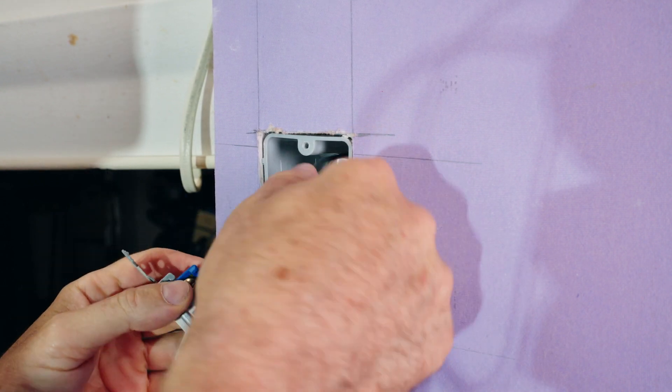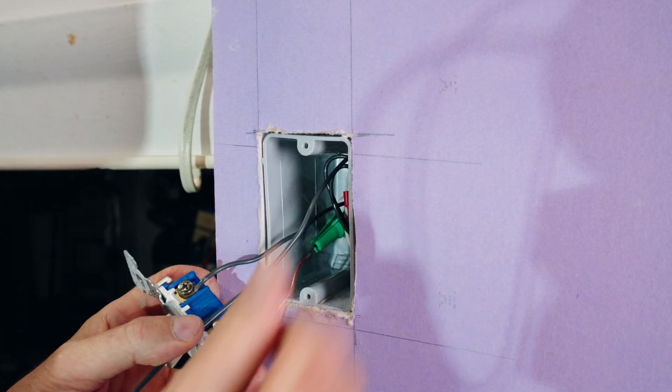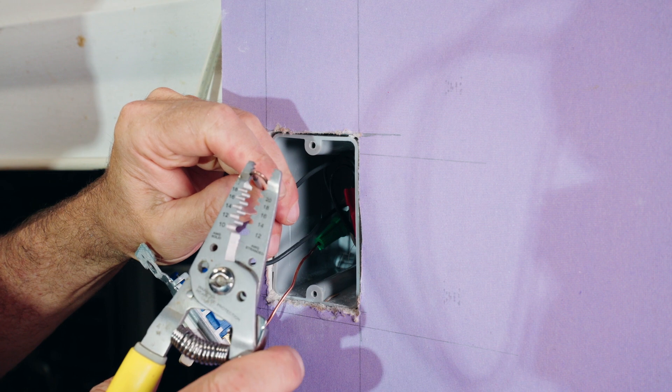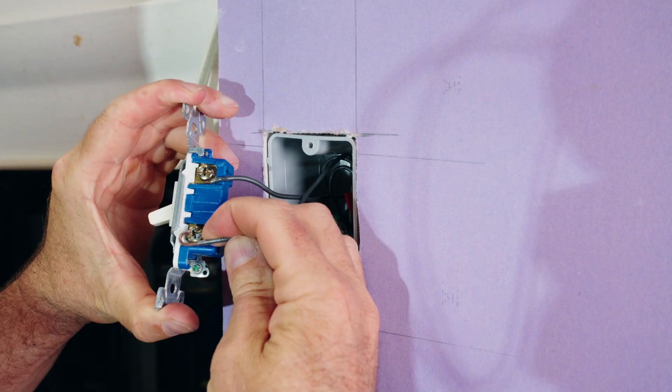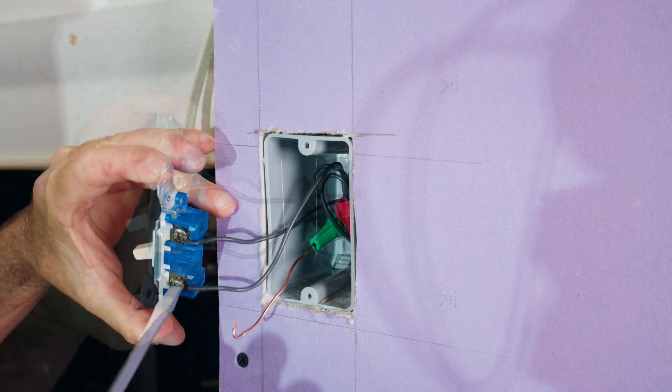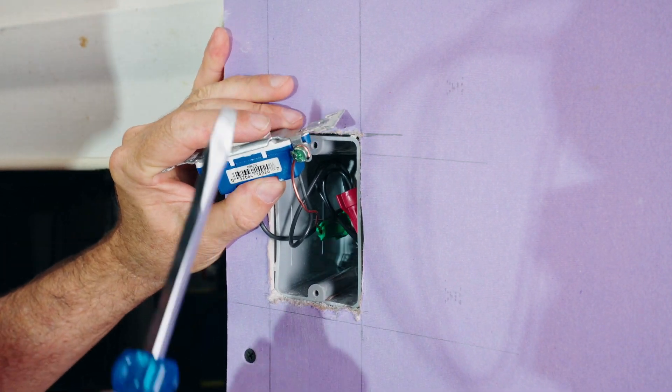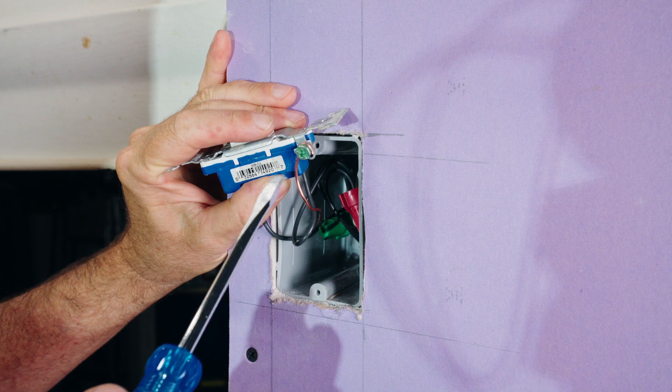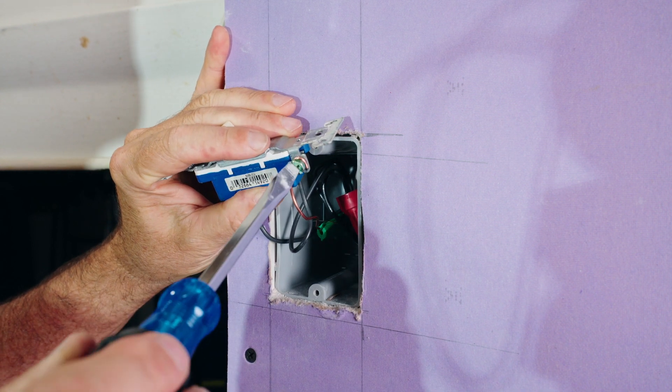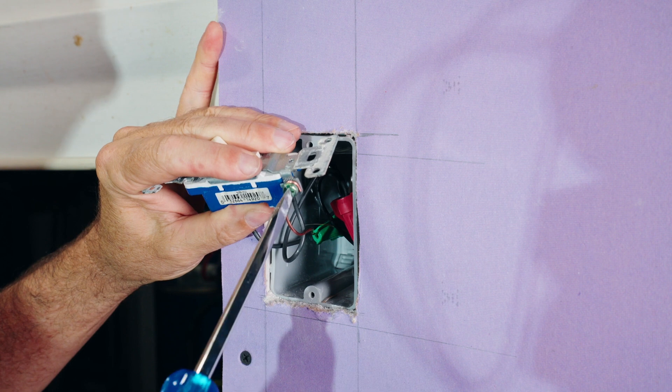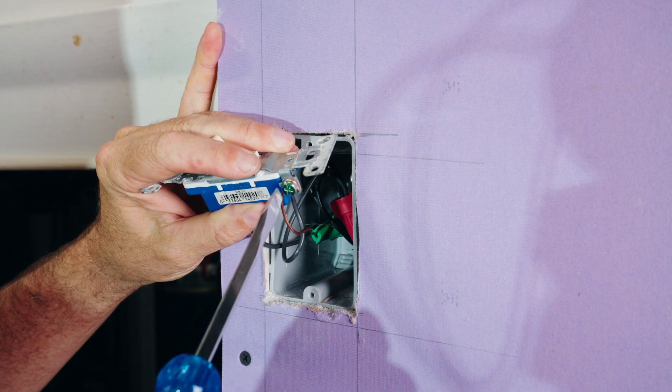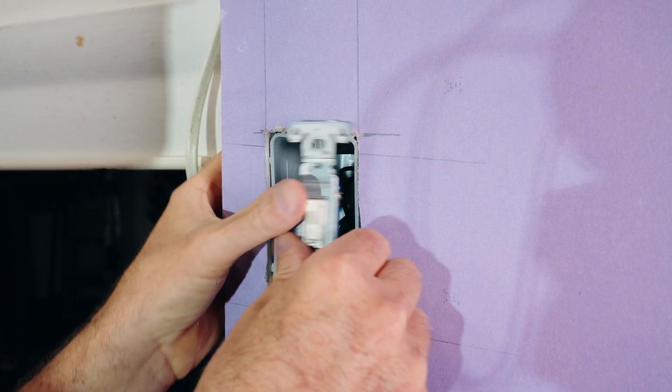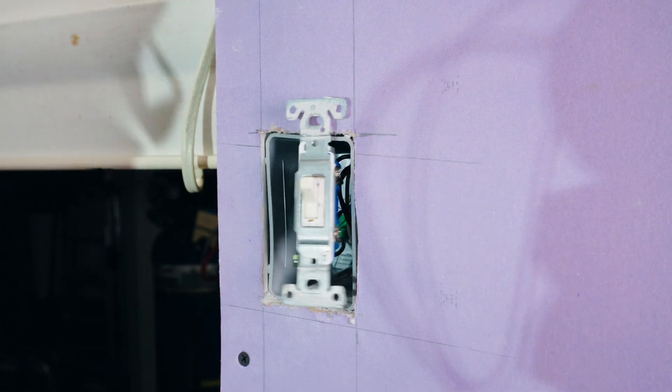We'll go ahead and cut this off so that it's equal with the other one. Bend it into a loop and connect it to our switch. By the way, if I didn't mention it earlier, when you're doing the loops on any connection, make sure the loop is going in the direction that the screw tightens. Because otherwise, when you tighten the screw, it'll loosen the loop. And we are ready to go.